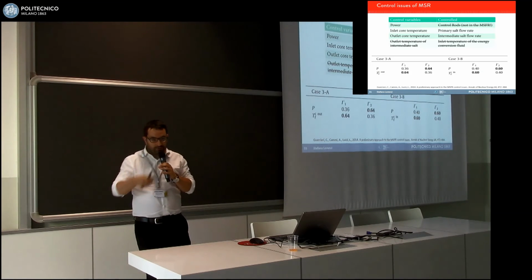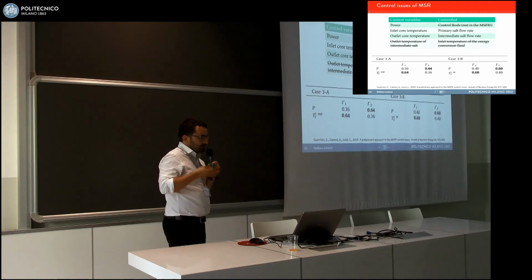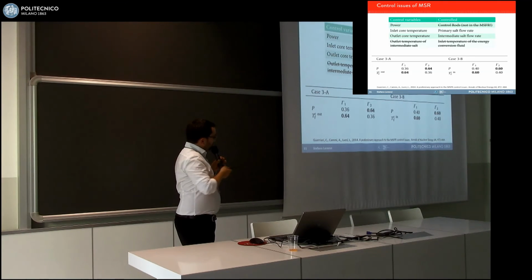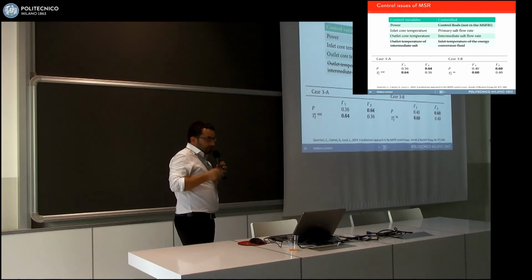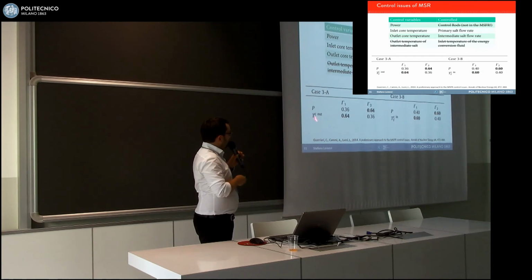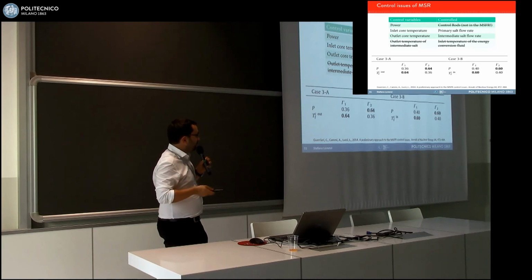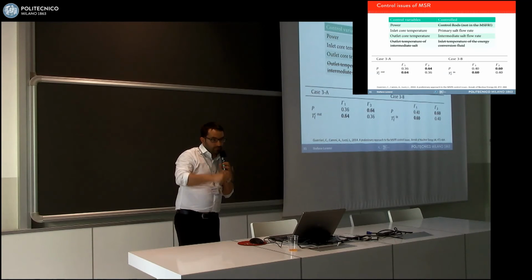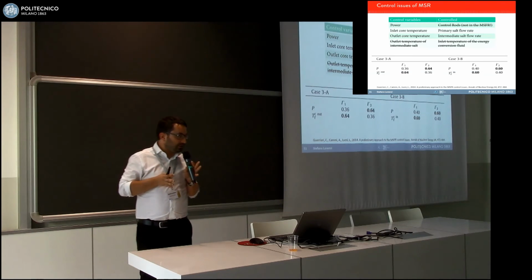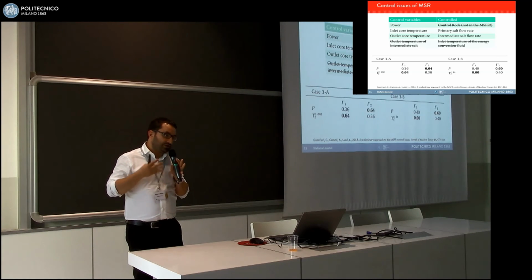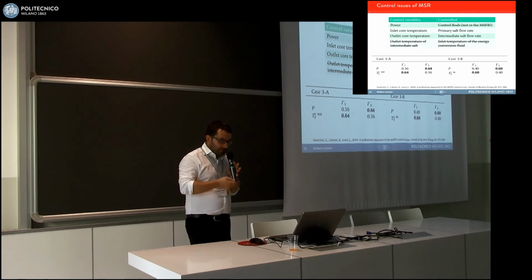But as I said before, what happens if we don't have control rods? Control rods are the main control variable that we have in a conventional reactor. This refers to a study performed during the EVOL project. We are able to manage the power and the temperature of the fuel, the outlet or the inlet temperature of the fuel, acting on the mass flow rate of both the primary and intermediate circuit. So basically, in the molten salt fast reactor, we don't have control rods, but we have strong negative feedbacks. This allows us to use the mass flow rate in order to control our variables of interest.